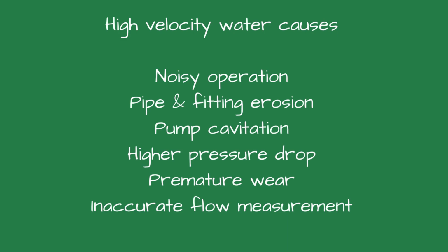High-velocity water acts like sandpaper over time. It can damage pump seals, control valves, thermostatic mixing valves, zone valves, and flow meters, all expensive to replace. Many balancing valves and flow sensors are calibrated for moderate velocities. High velocity can lead to false readings, making it harder to properly balance the system.